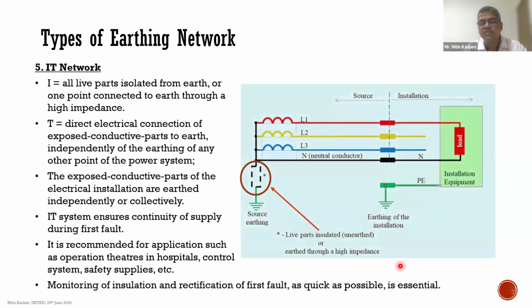Now, the next type of network is the IT network, which is the same as a TT network, except that the star point here is connected to the earth using a high impedance. This kind of system is generally used in operation theaters in hospitals, or control systems or safety supplies. The reason it is used, for example in operation theaters, is that in case of a fault, the supply should not get disconnected immediately, because if an operation is going on and the patient is on the operation bed, and the power supply goes off, the operation has to be stopped, which could be risky for the life of the patient. So in these cases, the first fault has to be rectified as quickly as possible, and therefore this type of network is specifically used for this application.